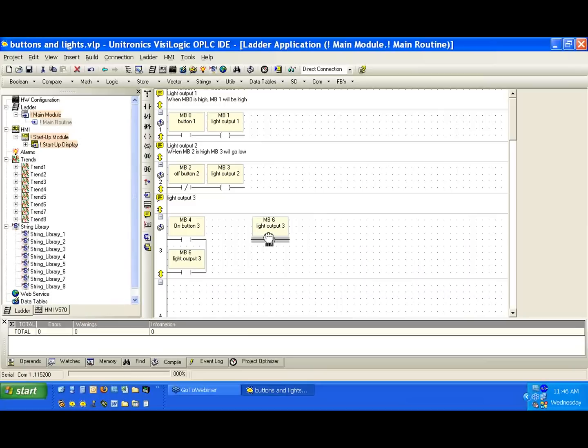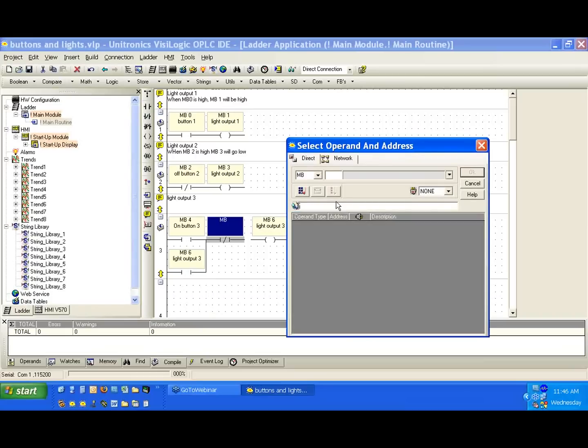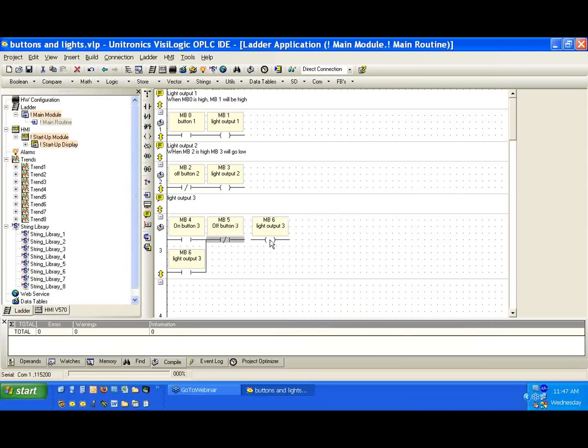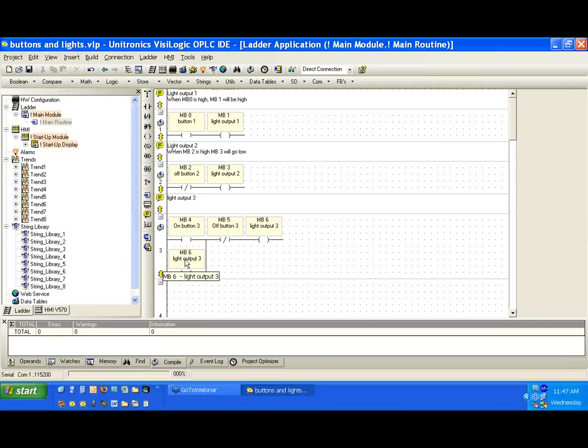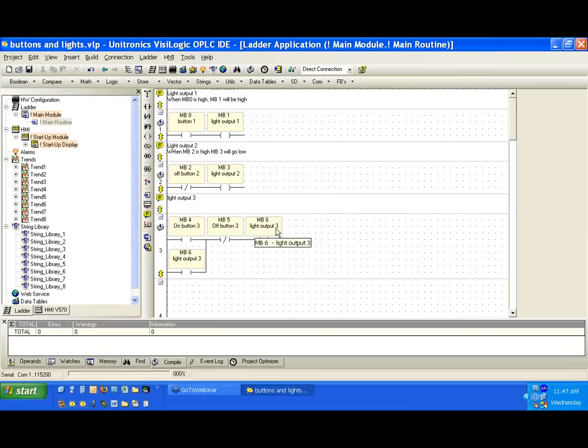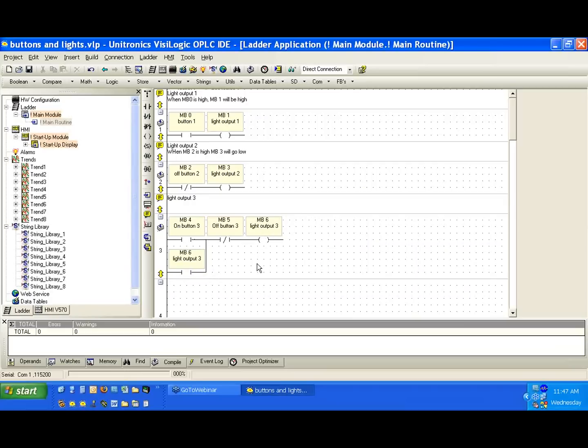I'm going to slide over this coil of MB6. And I'm going to add an inverted contact. Now what we're going to link this to is that off button 3. So I'm going to connect these again. And what we have here is, again, MB6 will stay high if MB4 or MB6 is high. Or if MB5 goes high, we're going to break the power flow to MB6. Since MB6 goes low and MB4 is low, the contact of MB6 will not be high. Therefore, the output won't be high at the end of the scan.